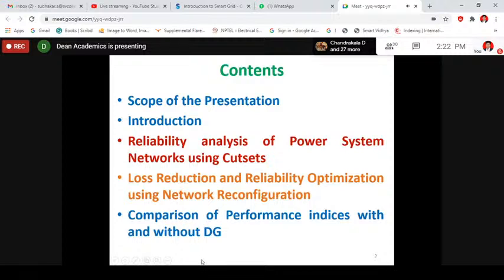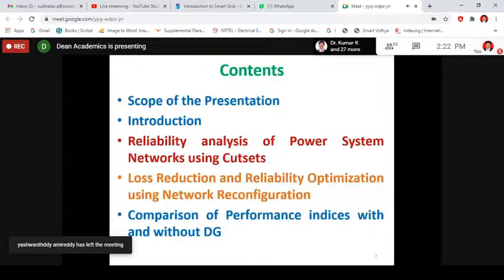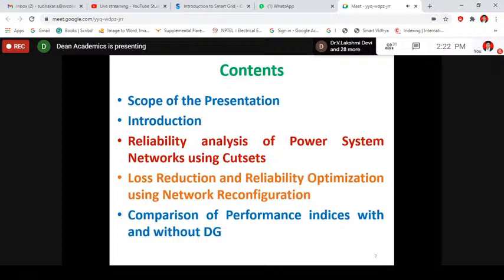Maintaining the voltage profile: ideally the base case value of 1.0 per unit should be maintained. Otherwise a tolerance of 2% was used earlier, 5% in literature from even 50, 30, 20 years ago. After 20 years, people realized 2% is too ideal. Although the most ideal is 0% voltage variation, then 5% was tolerable for a decade. Now people are saying up to 10% is considered. Less than 10% it is considered an ill-conditioned network.